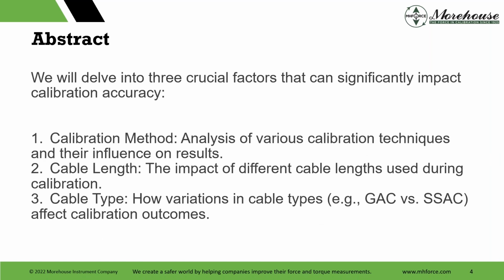There's more. These are the factors we're going to dive into. Calibration method: the techniques that you can use. There's dead weight, there's one with only one fixed point, with things hanging in air. Sometimes people are stacking weights, which is very unsafe in some systems, and sometimes not the best ergonomically, asking people to lift lots of weight, like 50 pounds, 100 pounds, stacking up to 2,000 pounds sometimes to calibrate this.